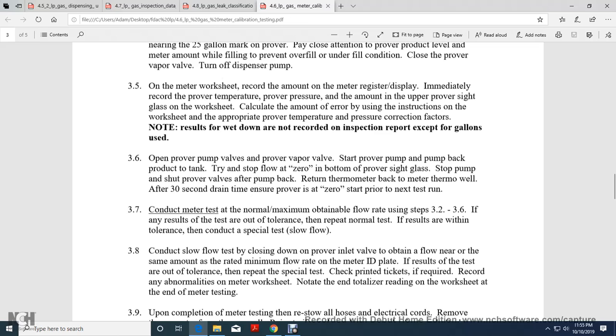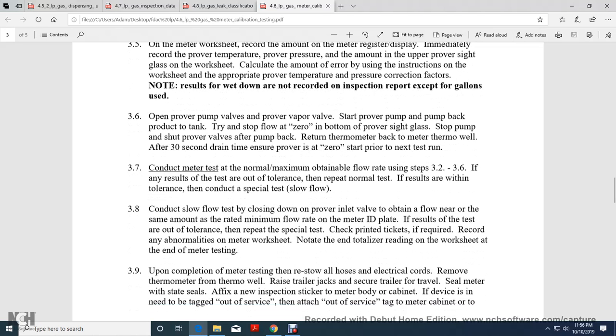Open the prover pump valve and the prover vapor valve and pump the product from the prover back to the product tank. Try to stop the flow at zero before the bottom of the prover sight glass. Stop the pump and shut the prover valves after the pump back. Return the thermometer to the thermal well after a 30 second drain time. Ensure the prover is at zero prior to starting the next test run.